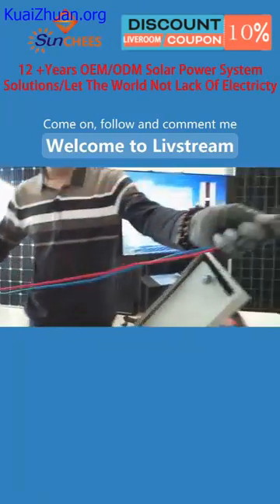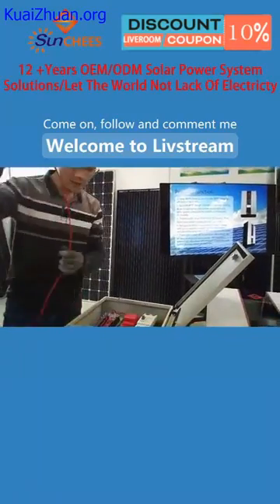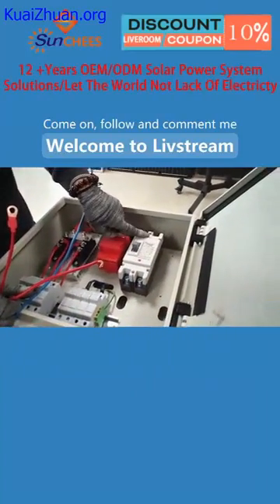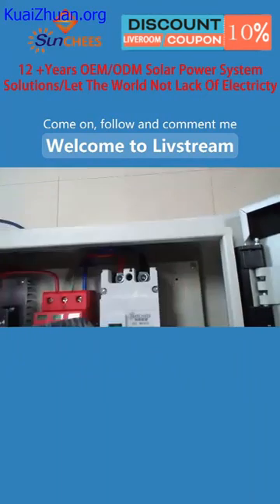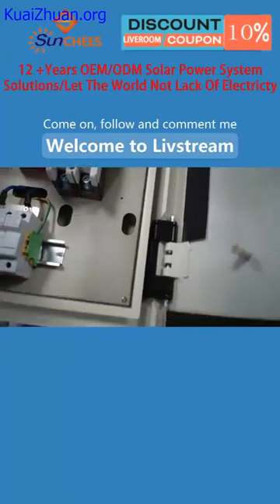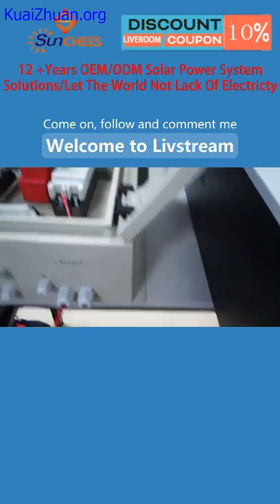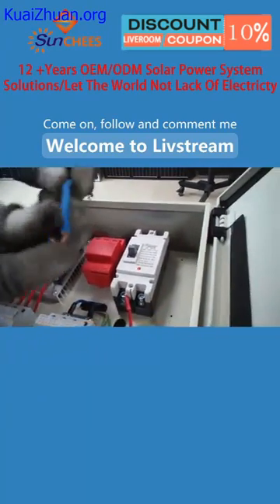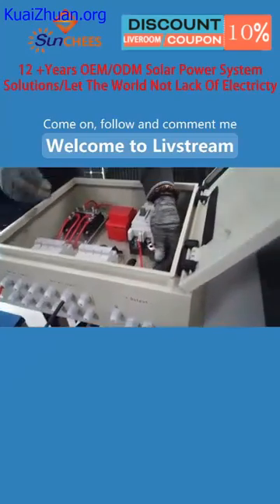These two cables are to connect the PV combiner and hybrid inverter. When you do this part, you need to check carefully inside the PV combiner that the color of the cables needs to match the cables on top of the breaker. You can see this is the breaker, and the left side is red color. That means this is the positive. So for the red cable, you also need to connect to the left side of the breaker. Okay. And the right side, it is blue color. That is negative on the right side. So you also need to make sure the blue color cable is on the right side. And then now let's do the connection.